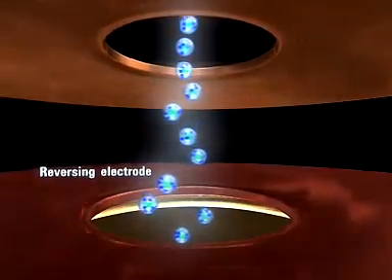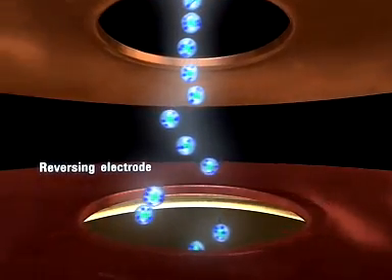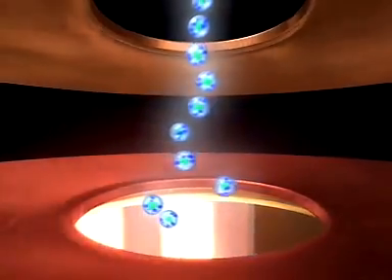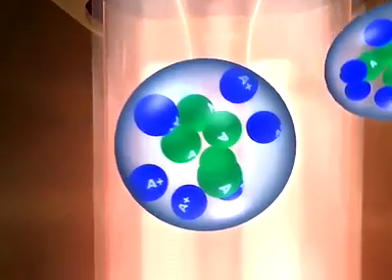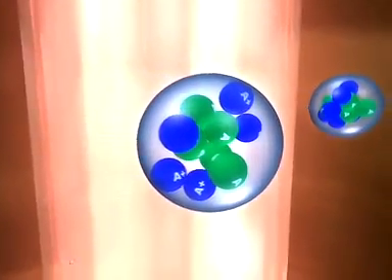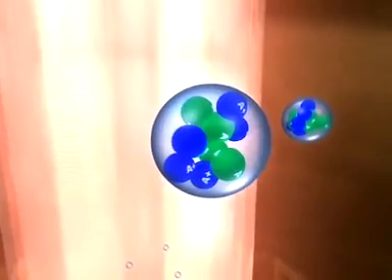The reversing electrode helps separate the electrospray and APCI regions of the ion source. Infrared emitters tuned to the absorbance wavelength of water provide fast, efficient drying of the aerosol, while preserving analyte ions and neutral analytes.